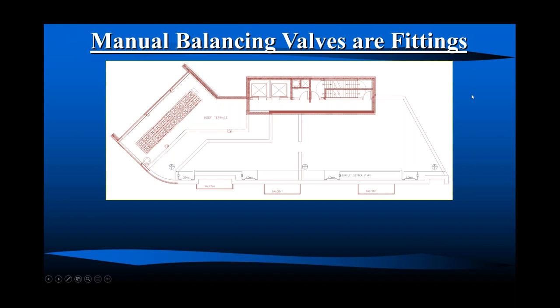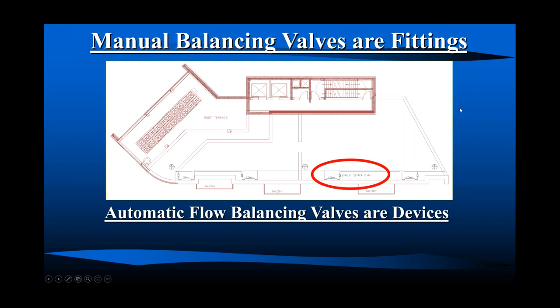Right, because manual balancing valves usually are considered a fitting. It's on the shelf somewhere, and it supposedly has to be adjusted in the field. So as long as you know the pipe size, it's kind of a fitting. I would consider automatic flow balancing valves more of a device. It's one more device, that's true, to put on your plans and schedule. If you think automatic flow balancing valves are what you want for your system, you really have to schedule them. They can make or break that sensible cooling only project. If you think that's a good idea, you really have to schedule.